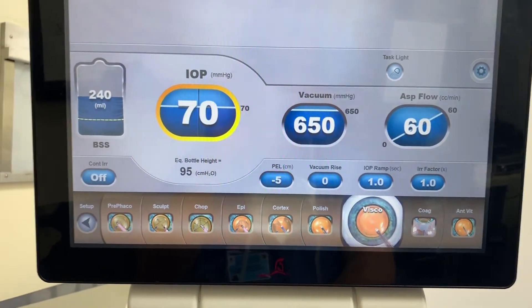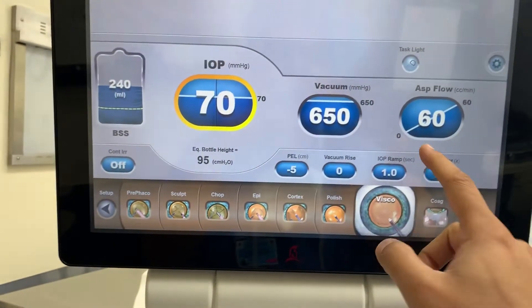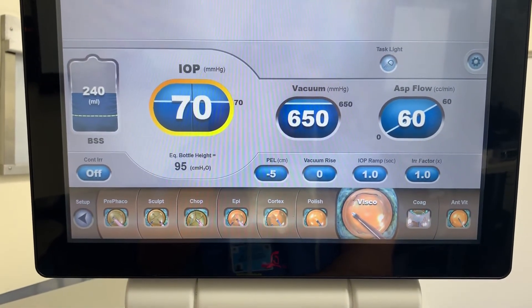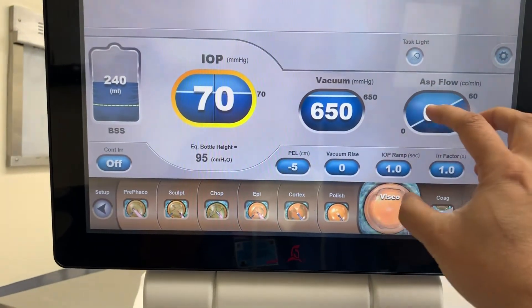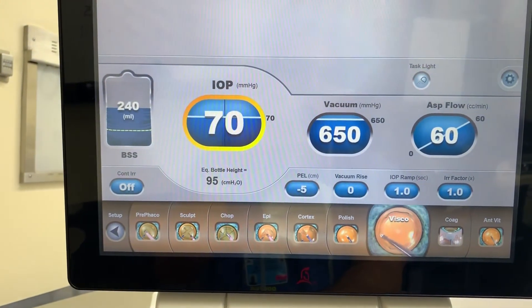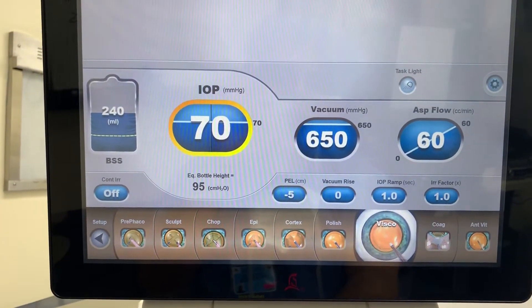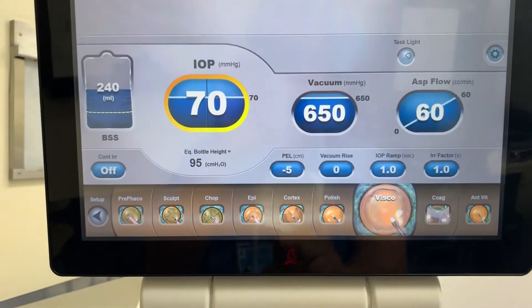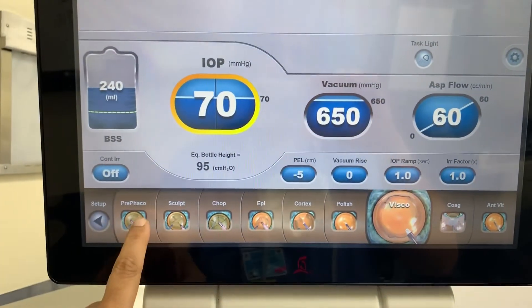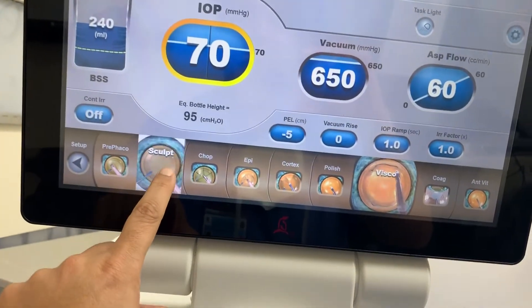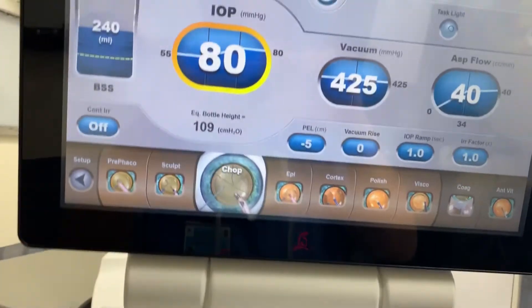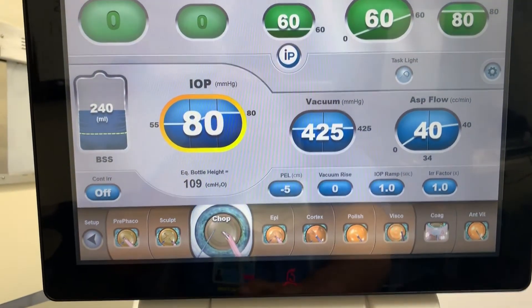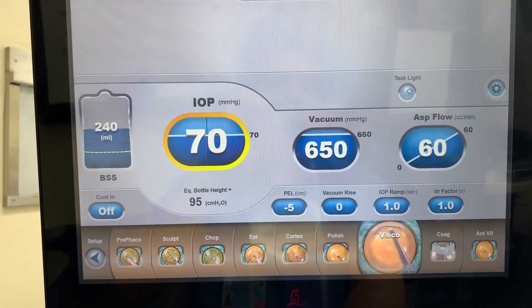For viscoelastic removal, we want a lot of current through the eye — about 60 cc's per minute — to flush out all the viscoelastic. With high outflow you need more inflow, so pressure goes up higher too, along with a high vacuum level, so any occlusion from viscoelastic, nuclear, or cortex pieces is cleared quickly. For most cases, I just use three settings: chop, cortex, and viscoelastic.